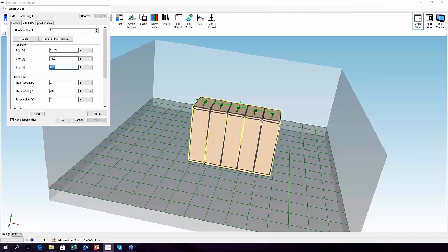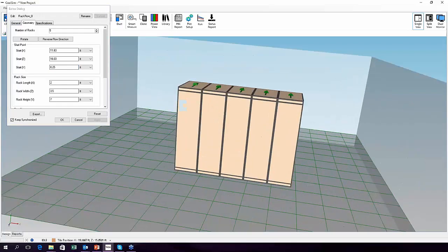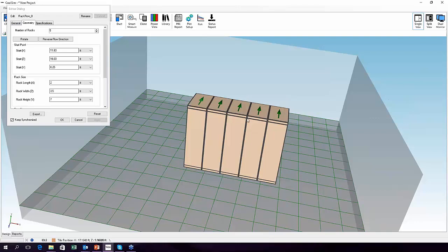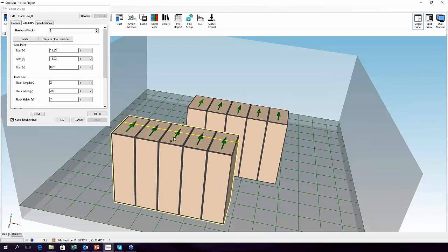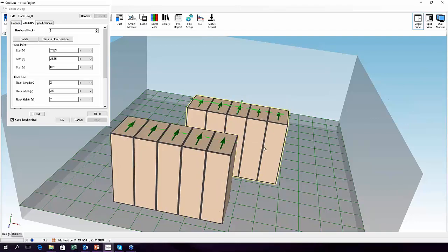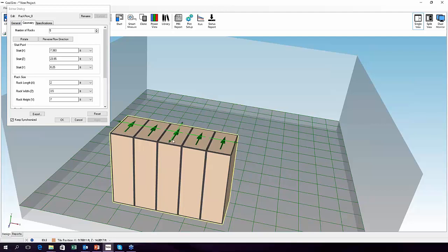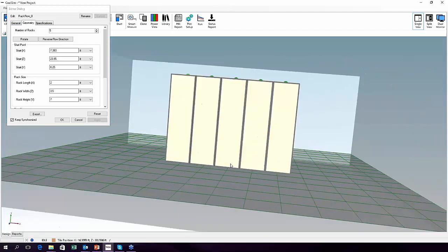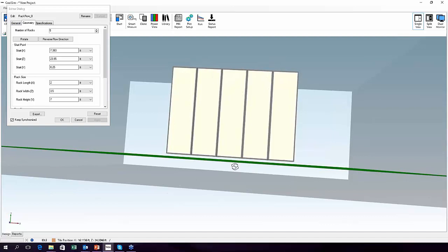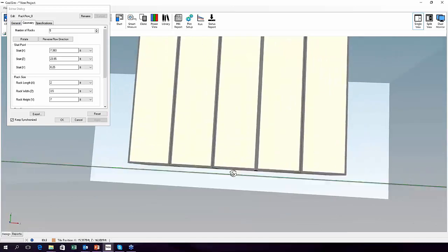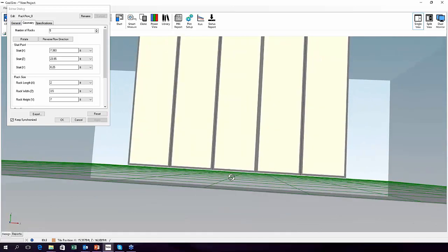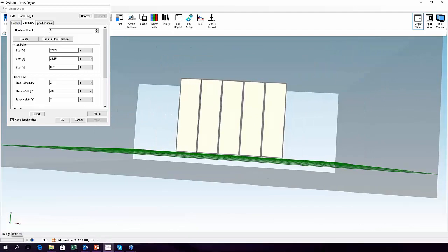But remember, when you do these things, you're increasing the density of the design. In particular, you're going to increase the mesh. The mesh is going to go up now because I'm going to mesh down to 3 inches. CoolSim will mesh down to a fraction of an inch if you make it.